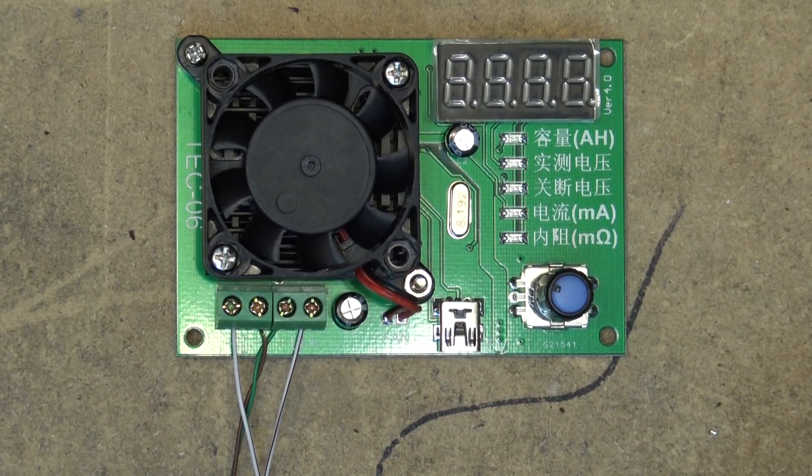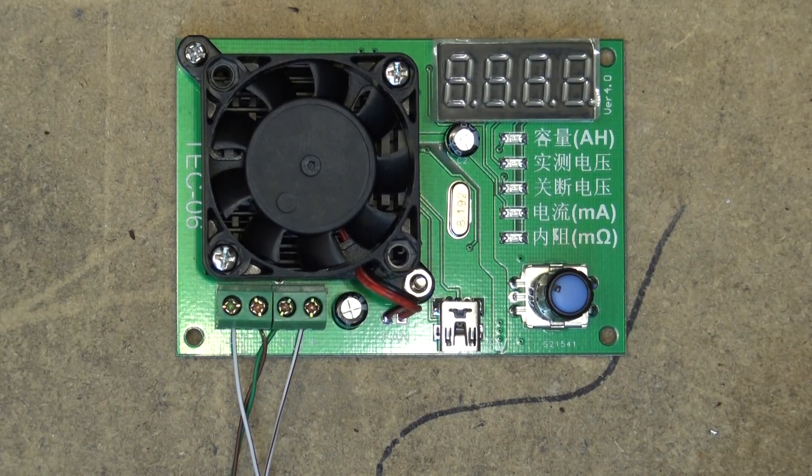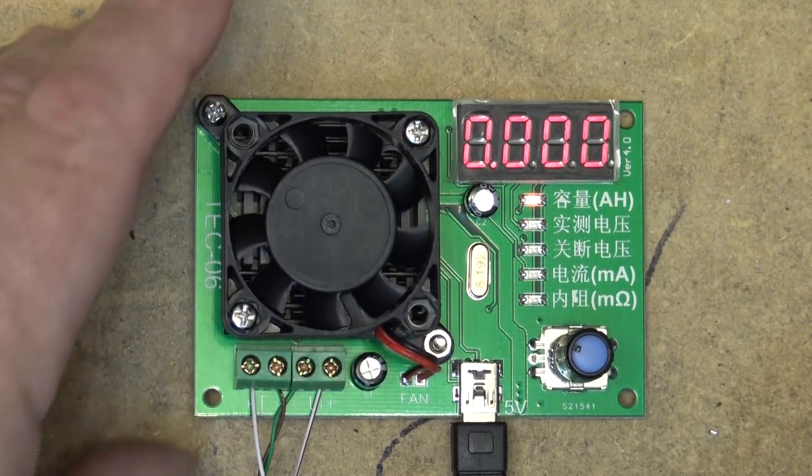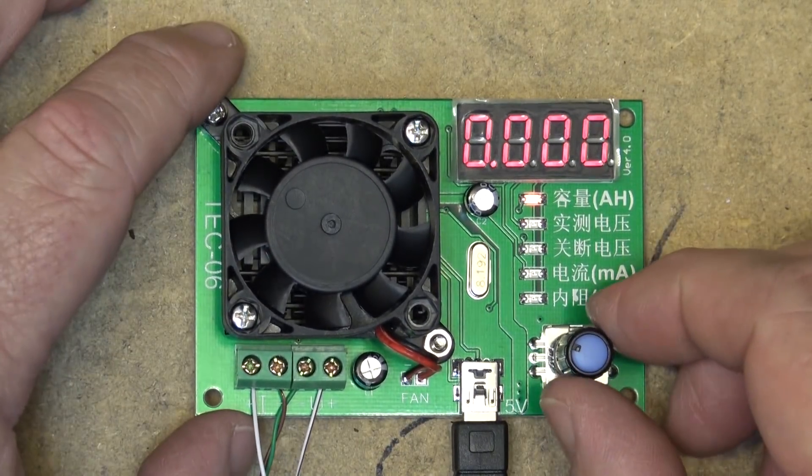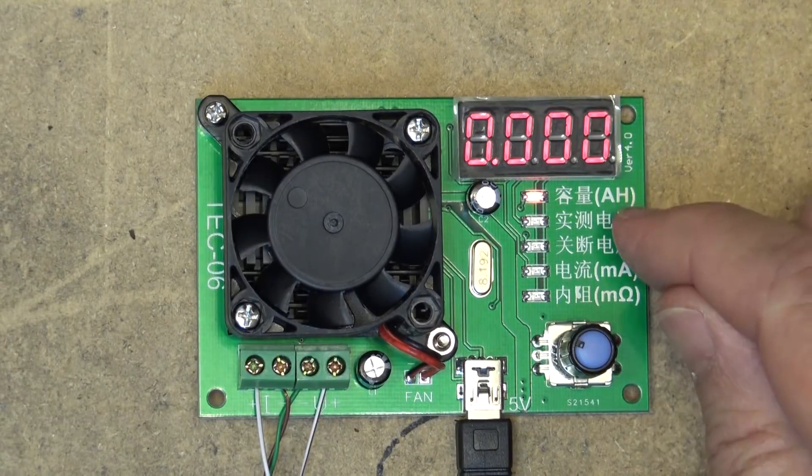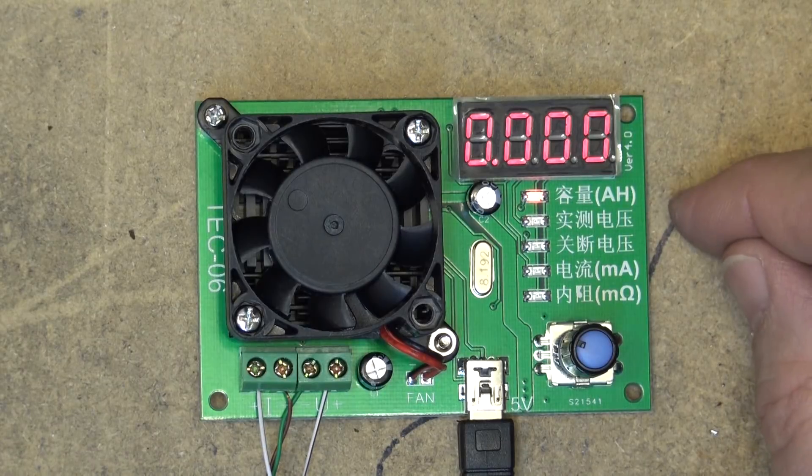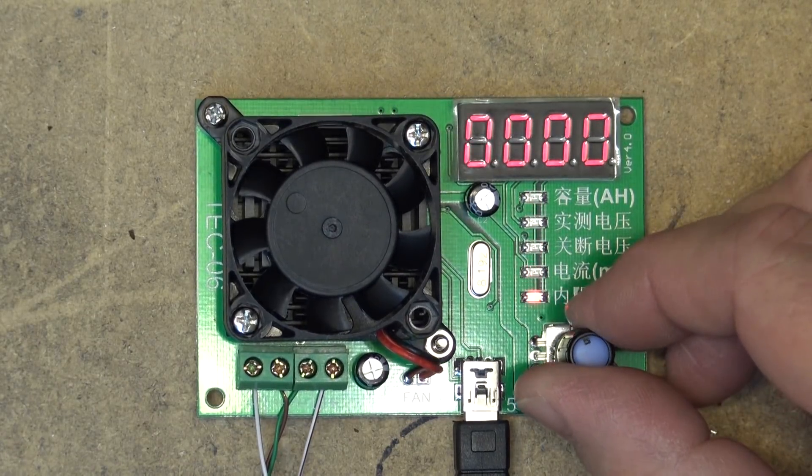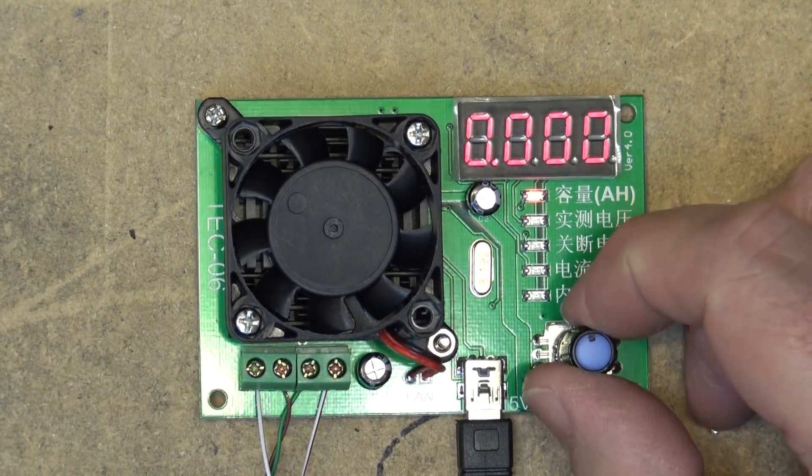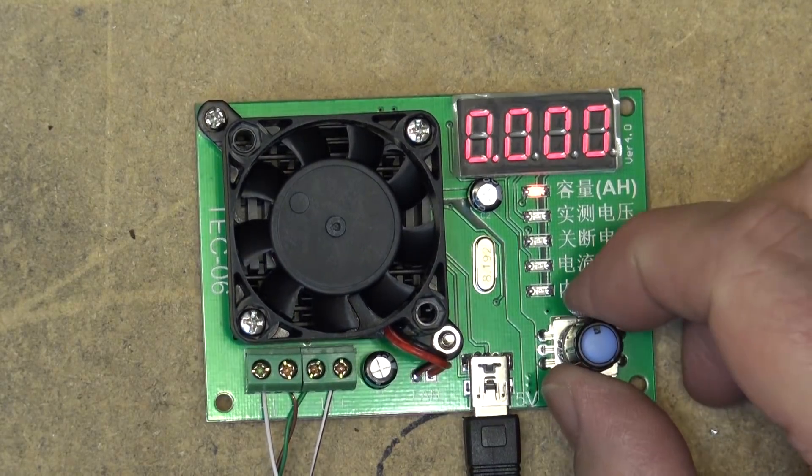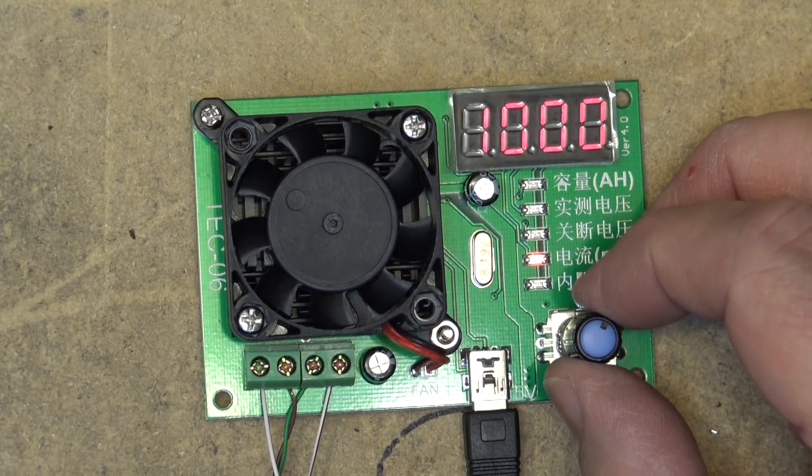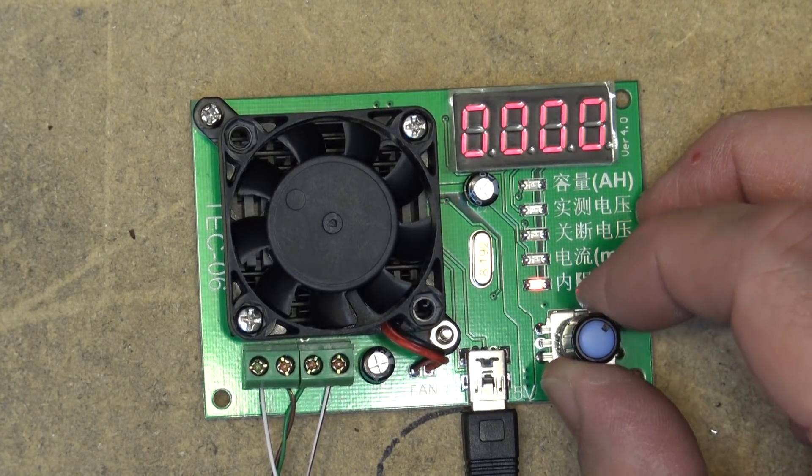Let's power this thing up, get my power cord. You can see we have a digital display and it looks like if we translate to English our five inputs here, our five settings are: your capacity in amp hours, your measured voltage, your shutdown voltage, the current in milliamps, and the internal resistance of the battery.